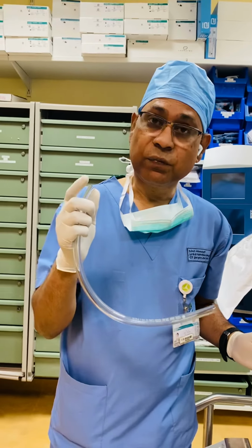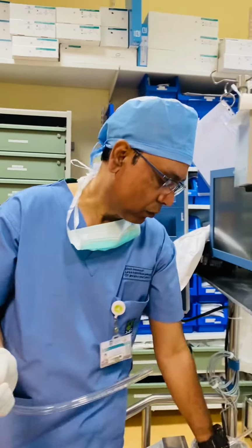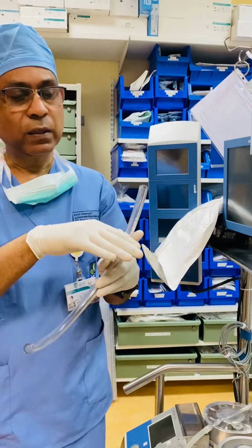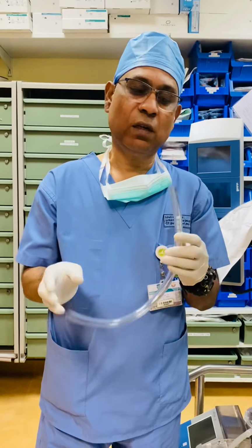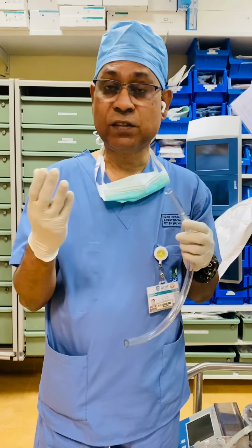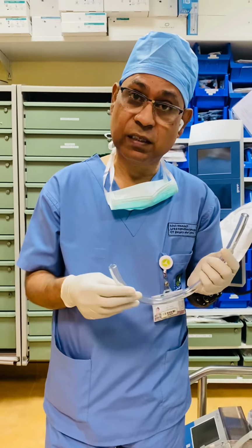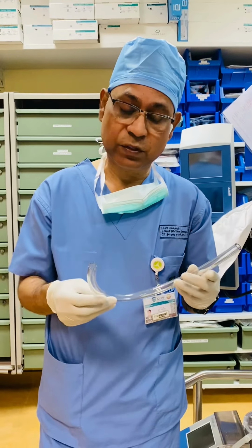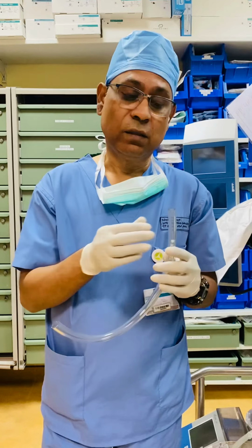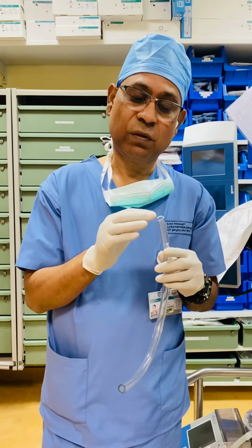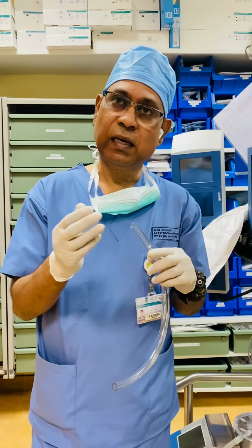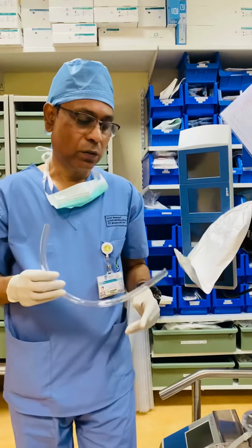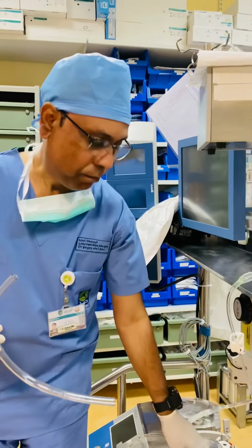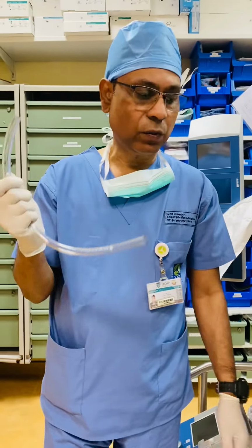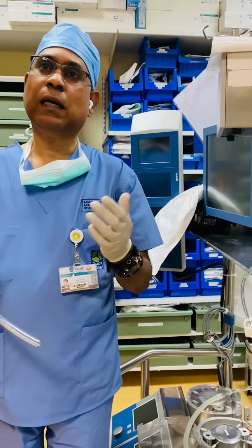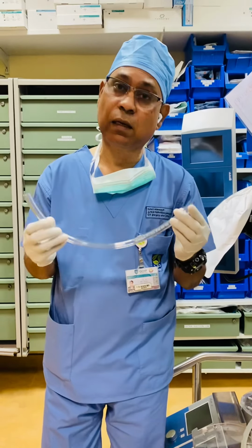If you use the PVC in the roller head, by the roller pressing on the tube continuously, there is a chance of inner breaking of the tube. Especially when you do hypothermia, like 18 or 20 degrees Celsius, during some complex procedure and your roller keeps running, the tube becomes rigid and there is a chance of particles of the tube breaking off and mixing in the blood. So the recommendation is to use silicone in the pump heads and the PVC tube just for carrying blood from the body and returning blood back to the body, hooked up with the connectors and the cannulas.